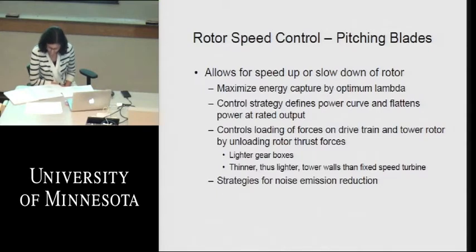And if we can control the loading of the forces on the drivetrain by pitching in and out, and then the tower thrust forces and such, we can get by with lighter gearboxes and thinner wall towers. And all this is cost. The more steel we have to put in to reinforce this for the higher loading forces for, say, a Type 1 versus a Type 3, is all cost. And so we can extract some of that cost just by these types of controls on the mechanical side and the electrical side. And pitching blades is a big part of that. And as I referred to, we've got noise emission control strategies where pitching the blades is the control methodology. The next slide.